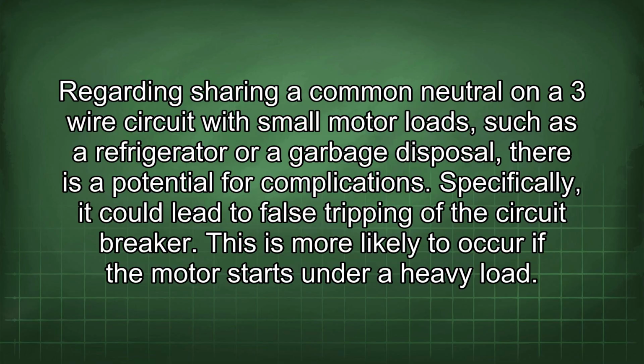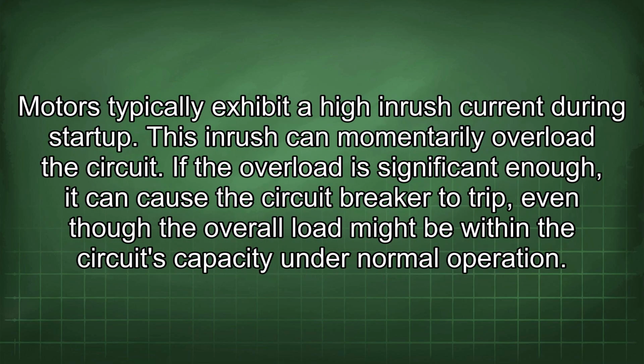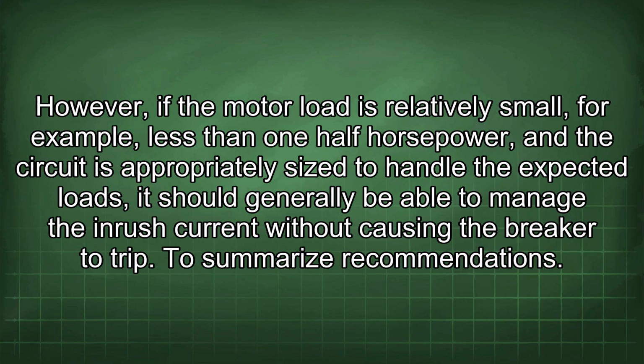This is more likely to occur if the motor starts under a heavy load. Motors typically exhibit a high inrush current during startup. This inrush can momentarily overload the circuit. If the overload is significant enough, it can cause the circuit breaker to trip, even though the overall load might be within the circuit's capacity under normal operation. However, if the motor load is relatively small, for example, less than 1/2 horsepower, and the circuit is appropriately sized to handle the expected loads, it should generally be able to manage the inrush current without causing the breaker to trip.